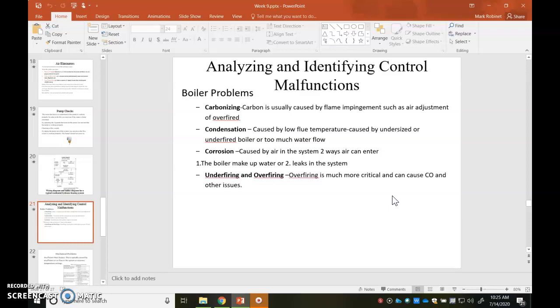Condensation. Condensation is where we're cooling the flue gases off too much. And you might do this if you have what's called a cold boiler, or too much water flow through the boiler, or there's a couple things there. Typically, that's already done in the design of the boiler. It's not usually something that you can make changes to.